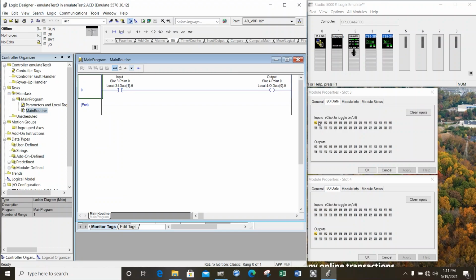We see over here that my inputs are still on and we can toggle them, but that change of state is no longer reflected in my monitoring window. Be very aware of whether or not you are online or offline. You have no idea how often programmers can sit in the factory bashing their face against the laptop for 3 hours wondering, why am I not getting data from the most recent changes that I made to the code, only to find out that at some point in time they went offline and they're looking at nothing. It'll happen to you, I promise.